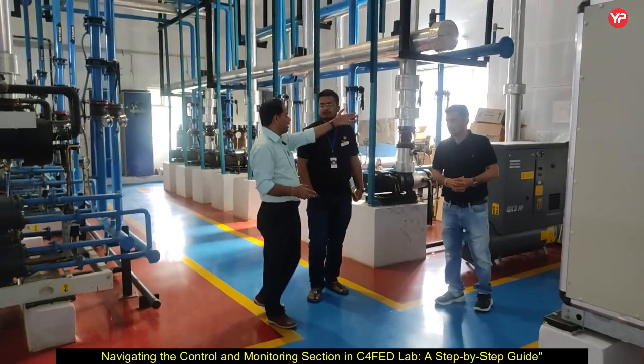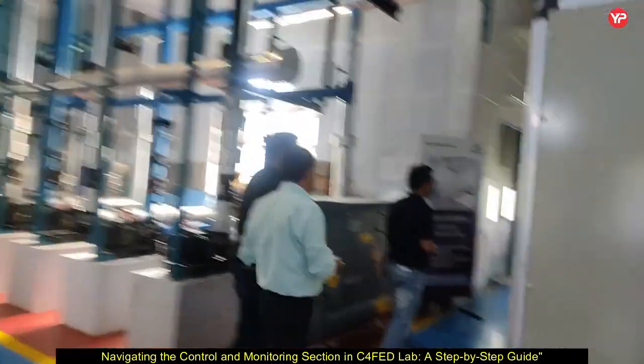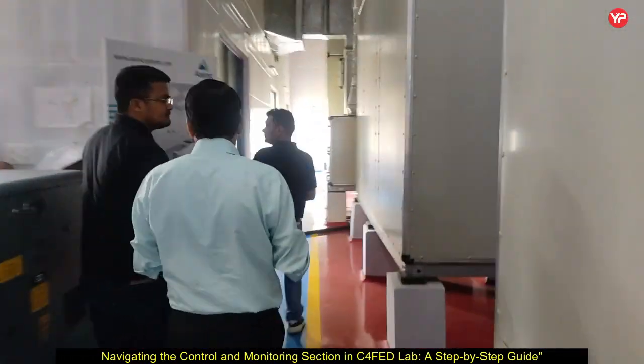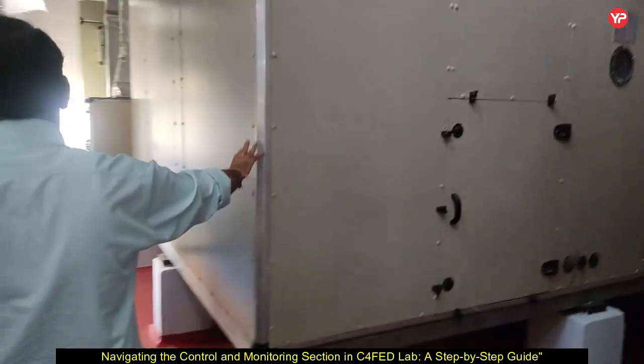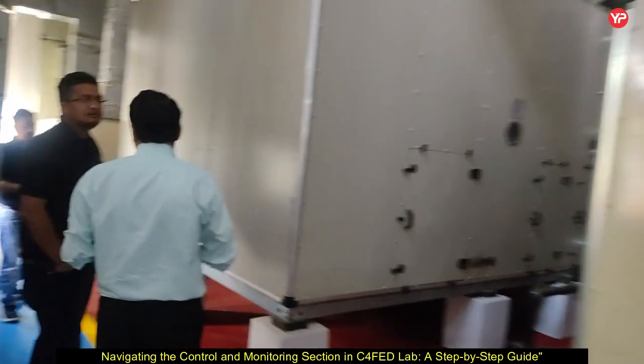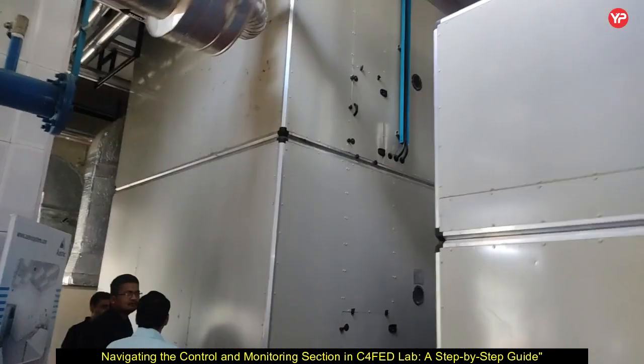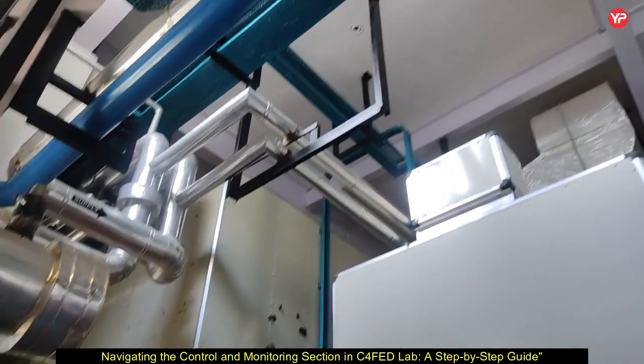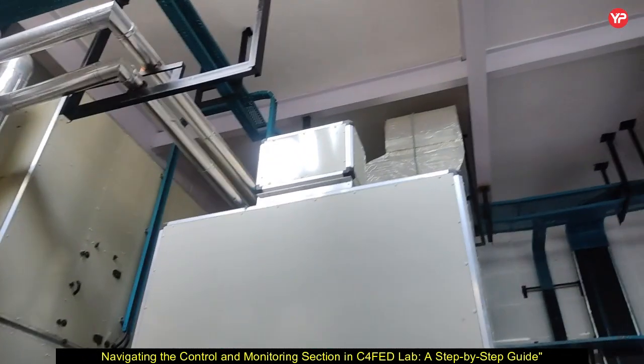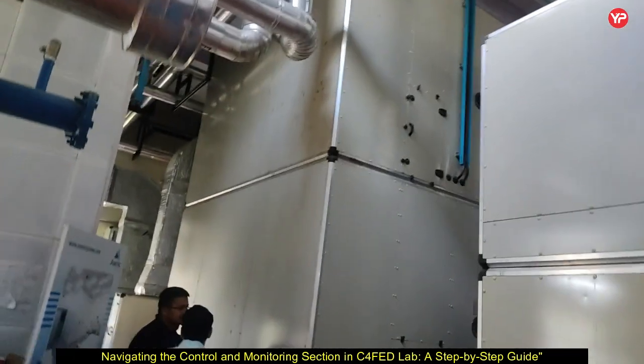If you see from that side, the next lab is class 1000. So this is the AHU, which is 25,000 CFM, for the class 1000. And you can see the size is larger than this one, because as the class gets cleaner, the air handling requirement increases.